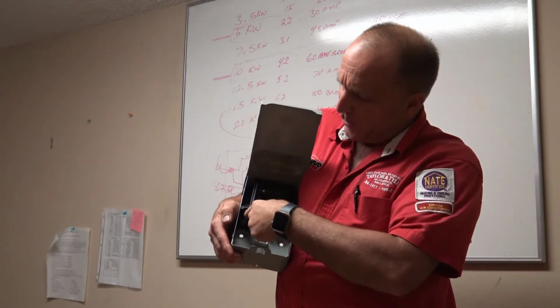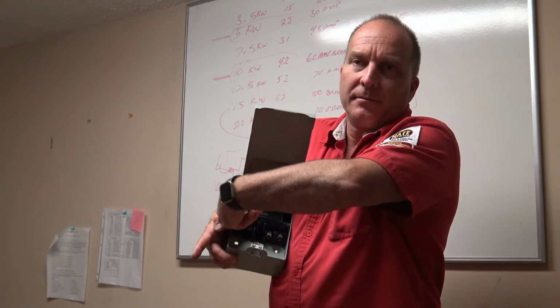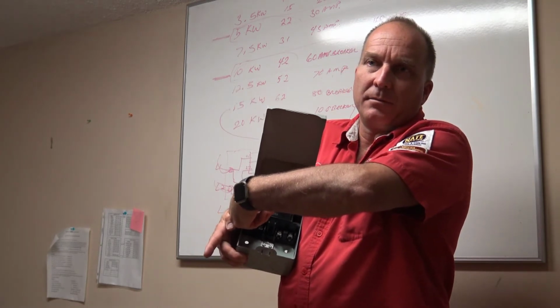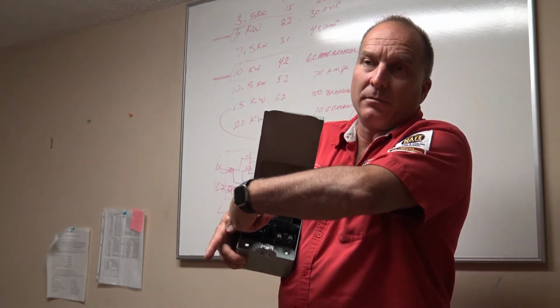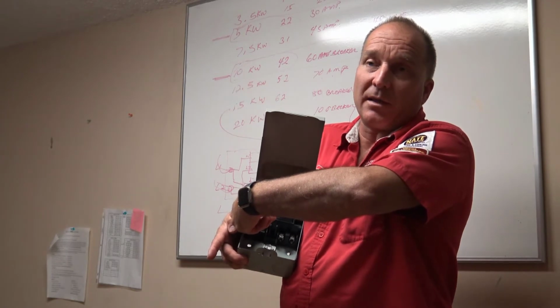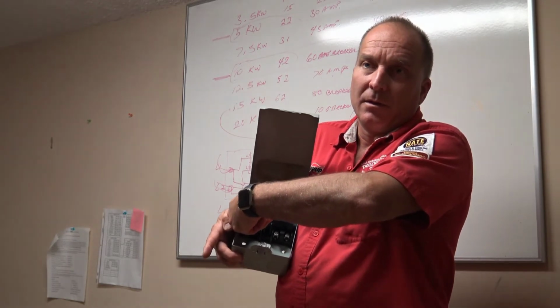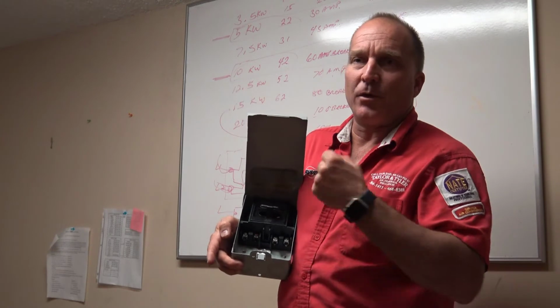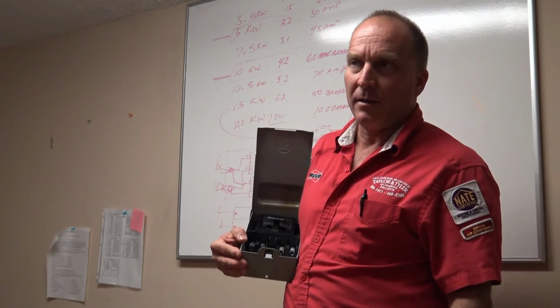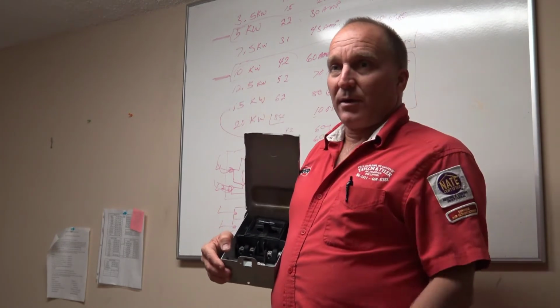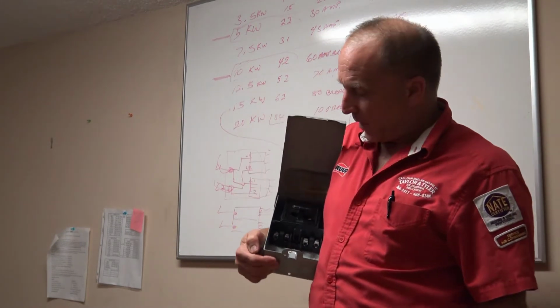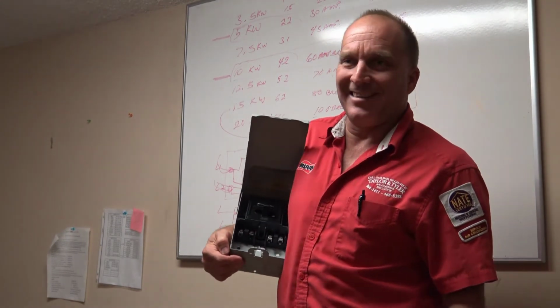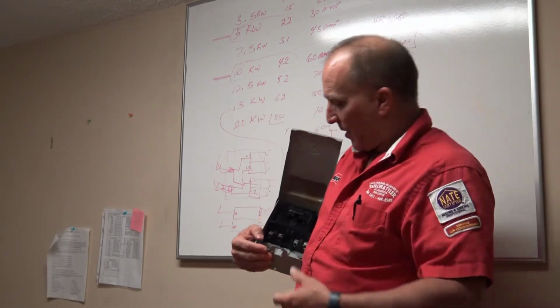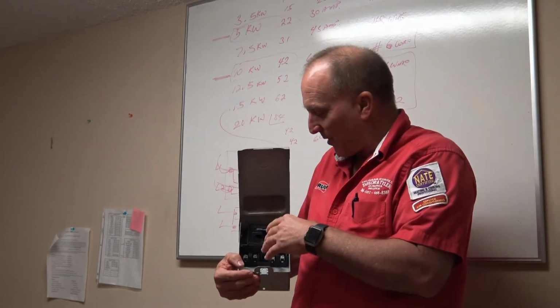Now what happens if your screwdriver touches the side right here? What's going to happen? It's going to short out. You're going to trip your breaker. Then you've got to go reset the breaker or replace the fuse. So should you turn the power off to this before you do it? Yes. Okay? Anytime you stick a screwdriver in something, you should kill your power. Now, how many people do it? No, I'm not going there. All right? I'm just not going there.